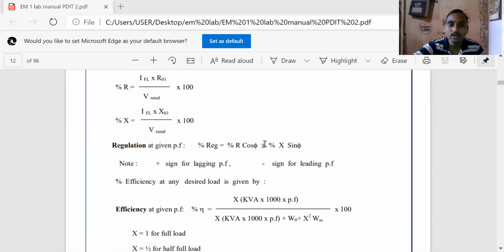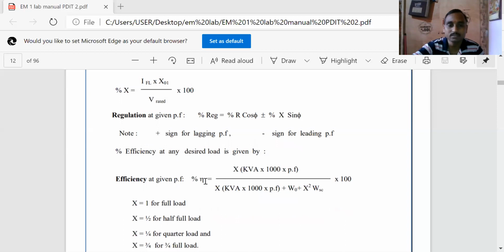Positive is taken for lagging power factor, negative is taken for leading power factor for calculation purposes. So while doing the calculation for both the lagging and leading cases, we'll take positive and negative. And efficiency at any desired load can be calculated by percentage efficiency is equal to X kVA into 1000 into power factor, divided by X kVA into 1000 into power factor plus W naught plus X square WSC, into 100. So W naught is the iron losses, and WSC is the copper losses.